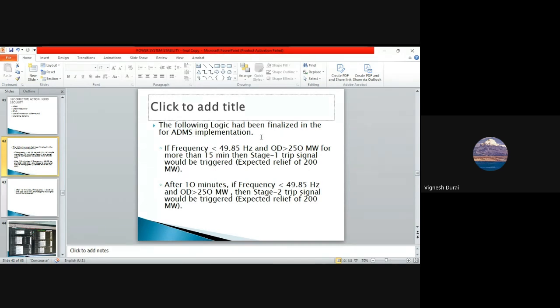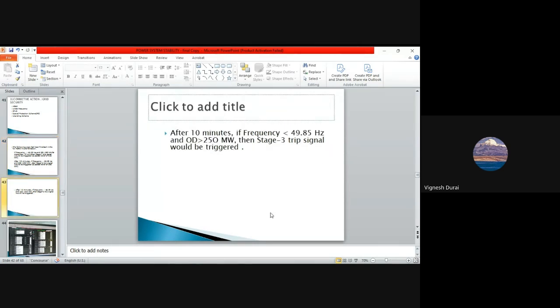Secondly, after 10 minutes, you will trip. Suppose this happens and you are going into tripping, you are shedding some loads. After 10 minutes, even if the frequency has not improved and the same condition prevails, you will go for stage 2 tripping, again giving 200 megawatt of relief. Again after 10 minutes, if the same condition prevails, you have to go for stage 3 tripping, which would again be triggered automatically.